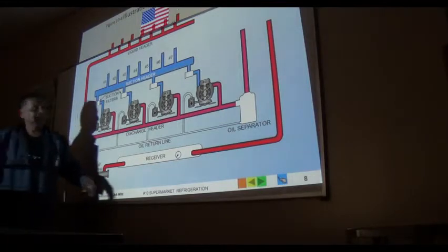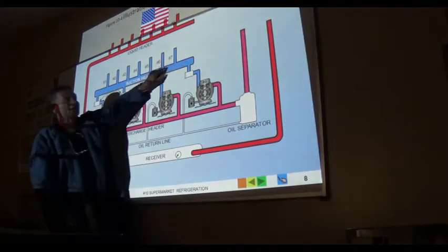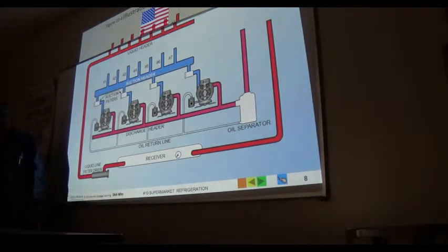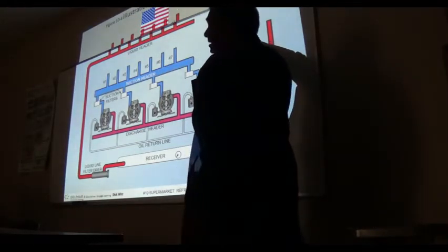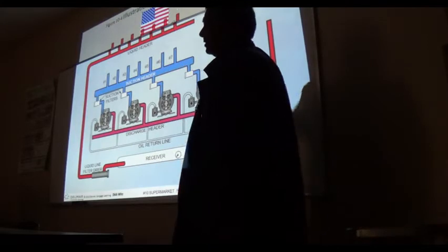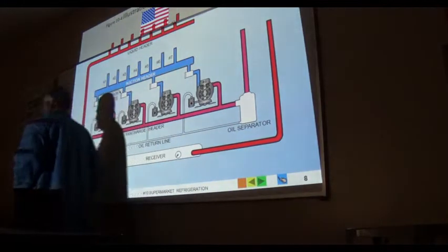And there always will be a vent for this, and that vent will be vented into the suction line. That discharge header. Yeah, you will. Straight up. Where does this go? This goes to the condenser. Wherever that's located, this goes to your condenser, because this is a refrigeration line. And coming off in here, there will be the vent that comes like that and goes into there, just in case you have a high pressure situation. It's going to vent back there. You don't vent refrigerant into the atmosphere. So vent it back into the low pressure side of the system.